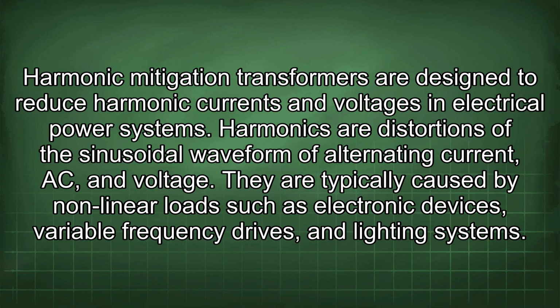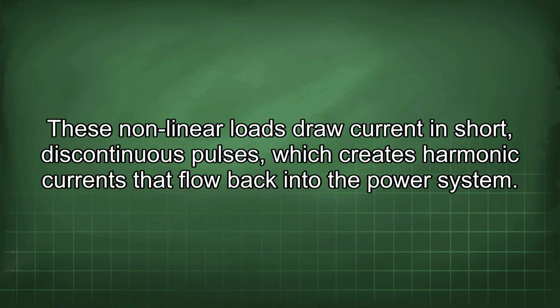Harmonic mitigation transformers are designed to reduce harmonic currents and voltages in electrical power systems. Harmonics are distortions of the sinusoidal waveform of alternating current, AC, and voltage. They are typically caused by nonlinear loads such as electronic devices, variable frequency drives, and lighting systems. These nonlinear loads draw current in short, discontinuous pulses, which creates harmonic currents that flow back into the power system.